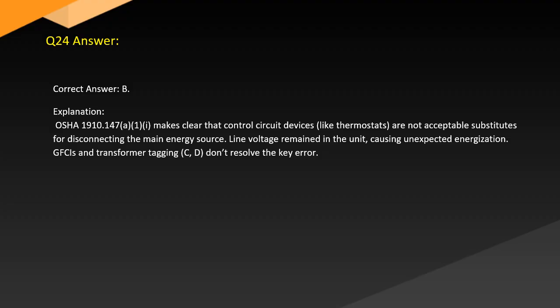Answer. Correct answer: B. Explanation. OSHA 1910.147 A1I makes clear that control circuit devices like thermostats are not acceptable substitutes for disconnecting the main energy source. Line voltage remained in the unit, causing unexpected energization. GFCI and transformer tagging, C and D, don't resolve the key error.